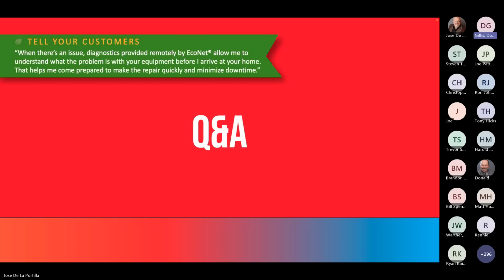If I can add to that just a little bit, you're going to have different types of mitigation strategies. As Jose said, we're going to fall under that M1, which is that minimum going to be a sensor of some sort. And then the fan coming on, as Jose said. Mitigation 2 gets a little more complex depending on the charge and the application, and that gets into how is the building being used. So you might have to bring fresh air into that room when all those bells and whistles go off. You might see solenoid valves where it's pumping it outside to the condenser outside the building, but that's not definite. None of that's definite yet. It's just up in the air that you may see those things.